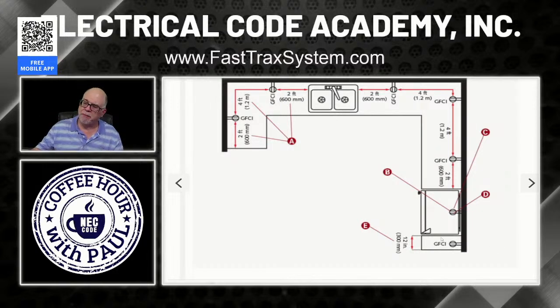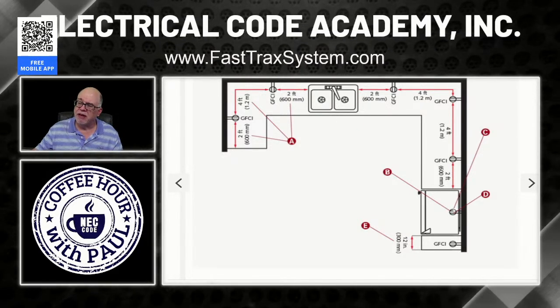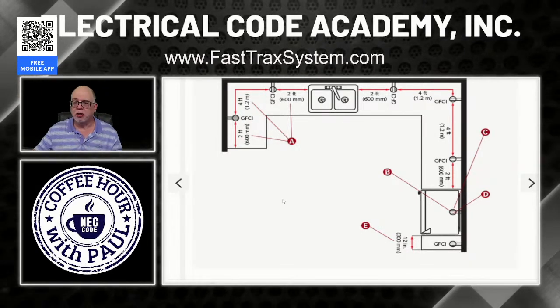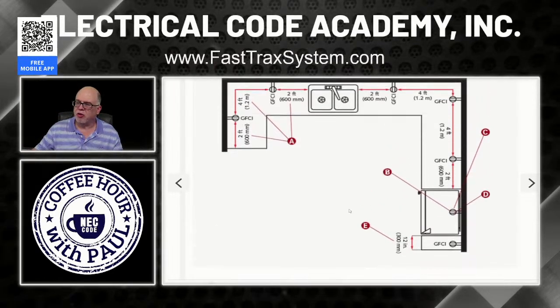Just remember, you can't put a GFCI receptacle back here. Why? Because in 210.8, they're required to be readily accessible. And it would not be readily accessible for testing if it was behind a big refrigerator. Okay, makes sense. So again, all these out here, you could put a GFCI in the very first one, and then everything downstream would be protected, or you could put GFCI in the panel and it protects all the receptacles in here. Okay. All right, so this is where we're at.